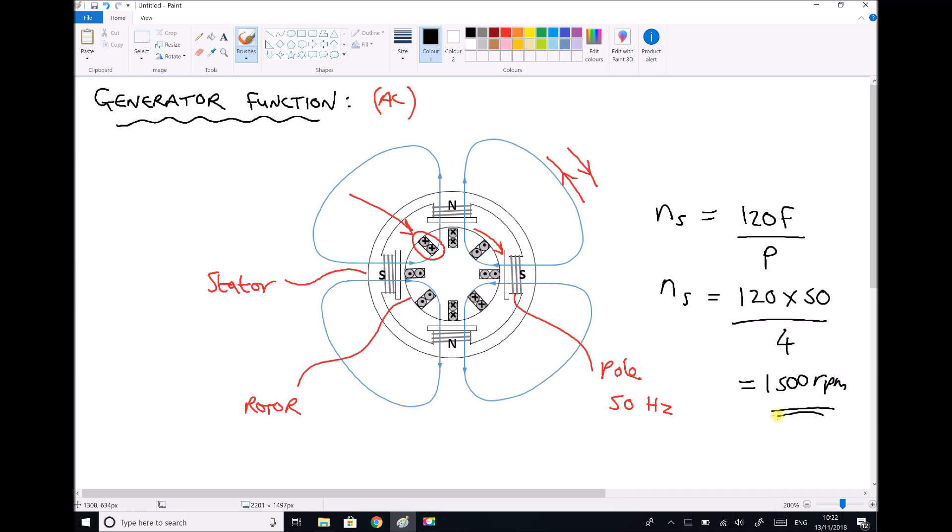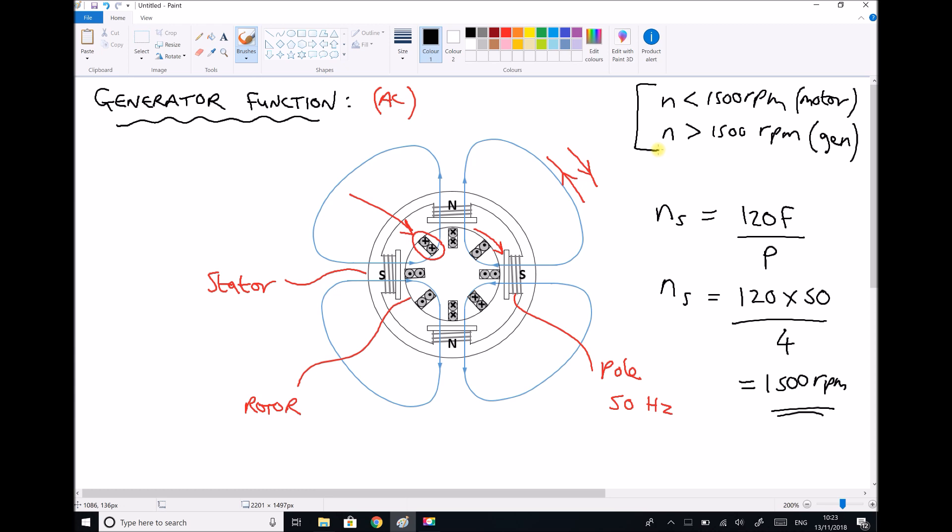What that means is this machine that can either be a motor or a generator: if the speed is below 1500 RPM, then this machine is going to be motoring or it's going to be a motor. If this speed is greater than 1500 RPM, then what we have is a generator. This principle is important for understanding different ways of generating energy. The key to remember is that 1500 RPM is the synchronous speed. Speeds above 1500 RPM means we generate electricity, and speeds below 1500 RPM means we're using electricity or we're motoring.